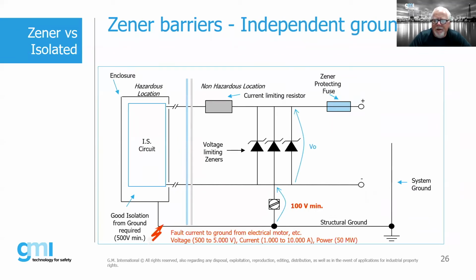So here's again a scenario we could see if we had a fault condition in the hazardous area that could potentially work its way up through the barrier and back into the device. So again, the key thing to remember when we're using Zener diode barriers is that we have to make sure our structural ground is separate from our clean earth. It must be a separate earth. That's the important thing to remember.